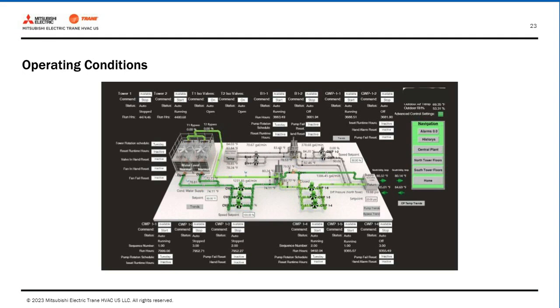If you look at the green lines on the slide, those are the above ground condenser water loop through the building and then out to the cooling towers. And those are separated by a big plate frame heat exchanger. And then the gray lines at the top of this little gray concrete pad represent the geothermal loop that runs underground. There's also a plate frame heat exchanger in between the geothermal loop underground and how we connect to this green building condenser water loop. So both loops have a heat exchanger that they utilize.